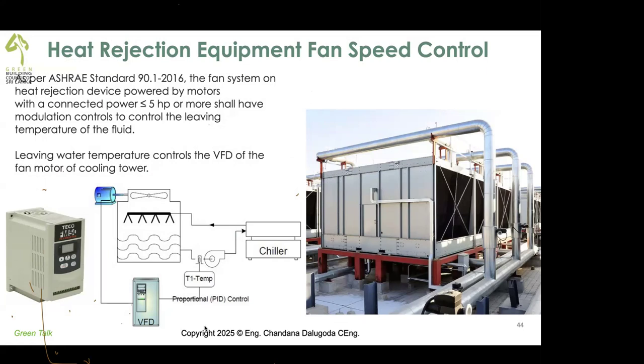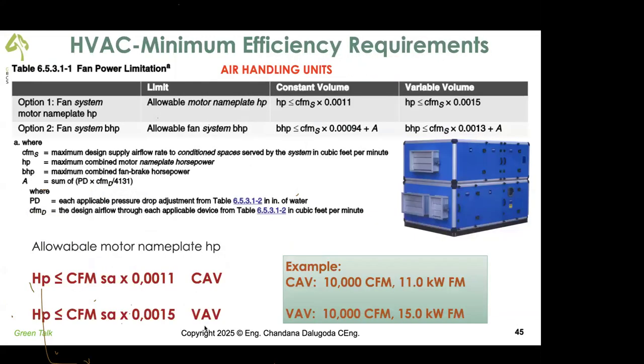Air handling units are similar, with a fan power limitation. So there's a little equation. For constant volume, we can calculate horsepower for a given supply air flow. For example, 10,000 CFM, 11 kilowatt. You can't have a higher motor than that.